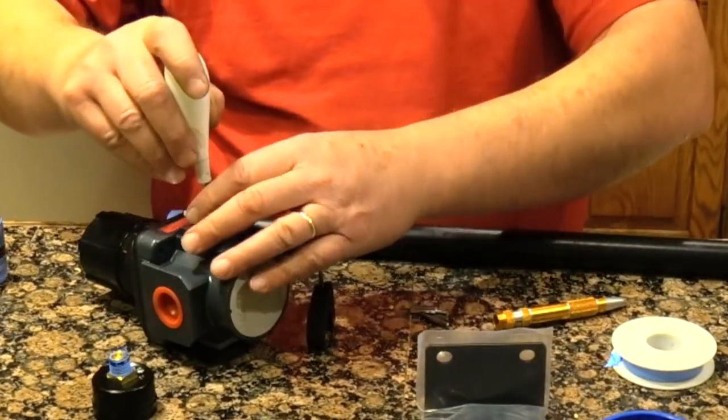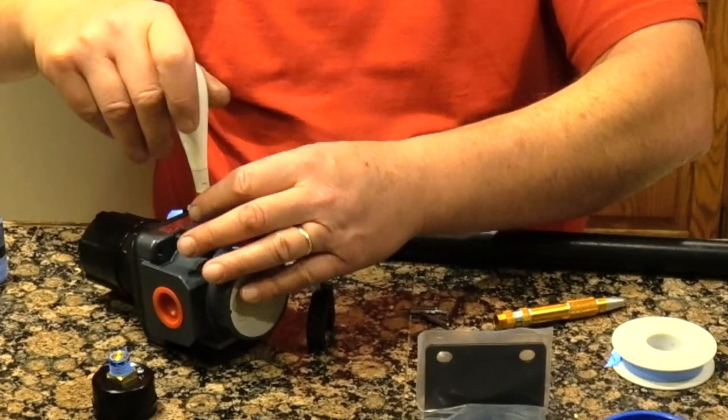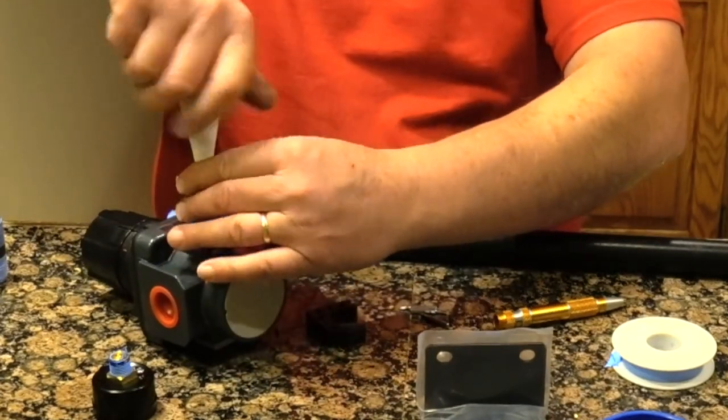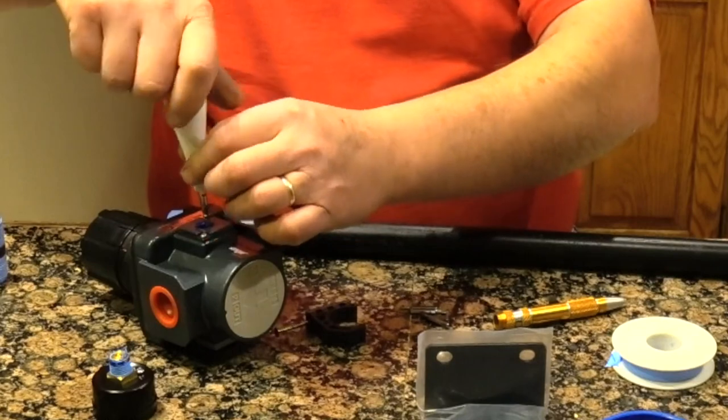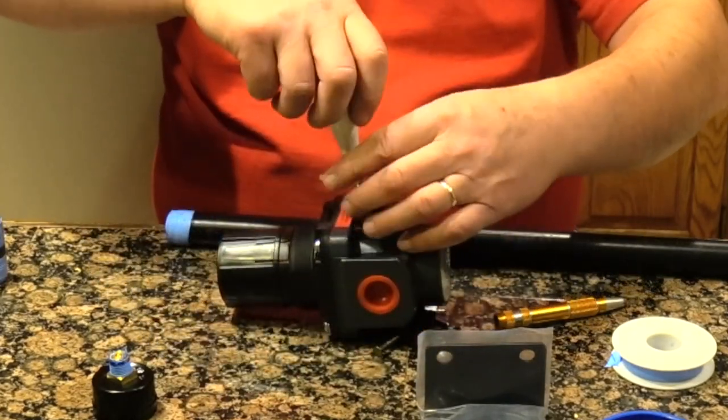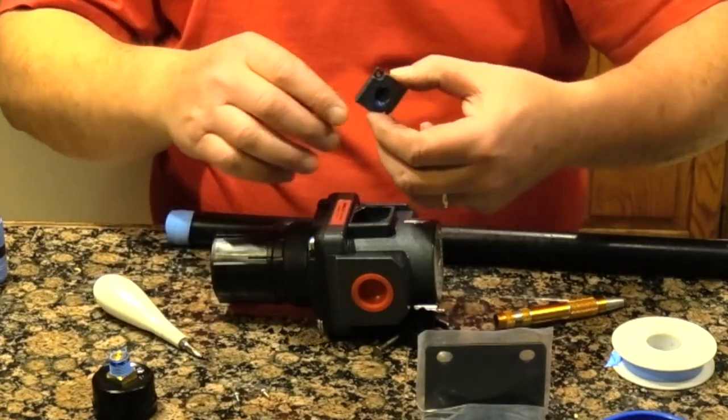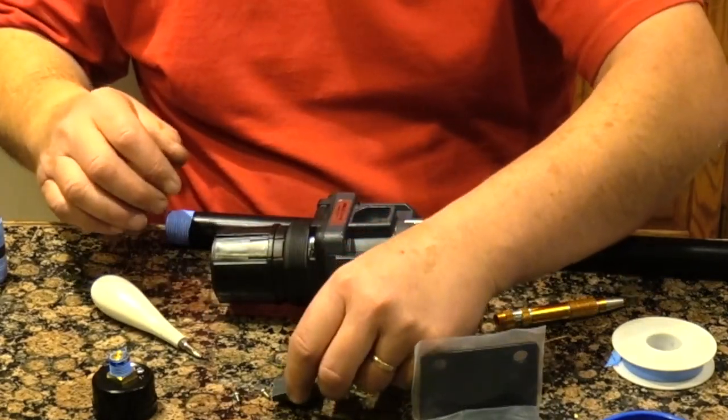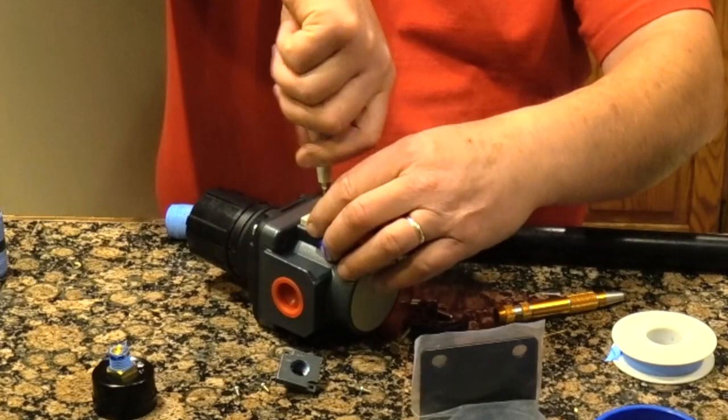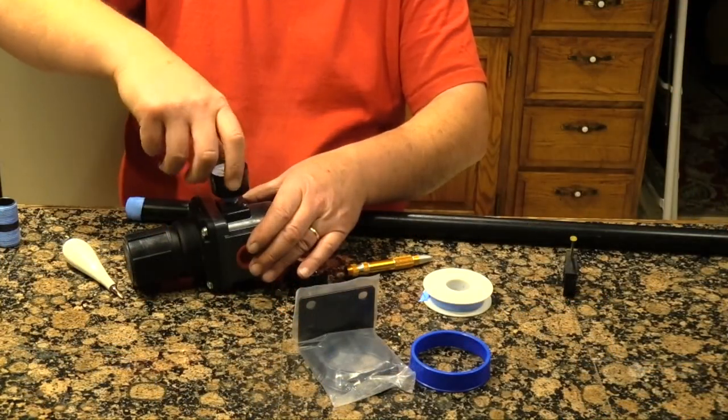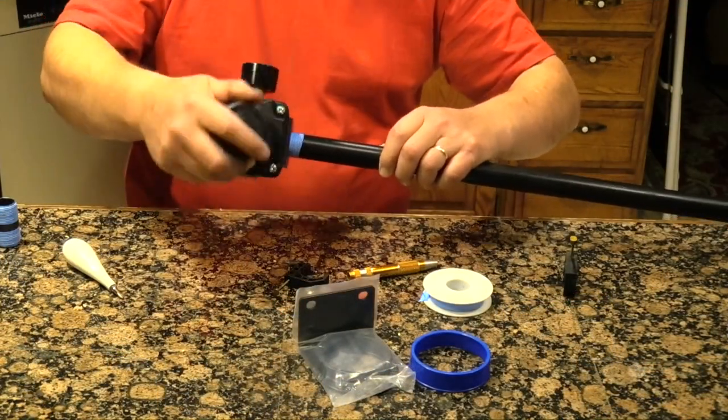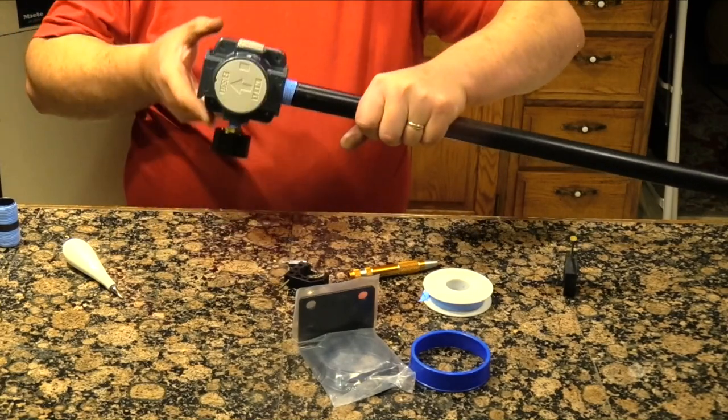I purchased a Milton brand air pressure regulator and moisture separator with a one inch capacity. Milton produces one of the highest quality air pressure regulator products in the industry. To change the regulator mounting direction I have to swap the gauge mount with the dummy plate on the reverse side. Be sure to observe the airflow direction as indicated by the arrow on the top.